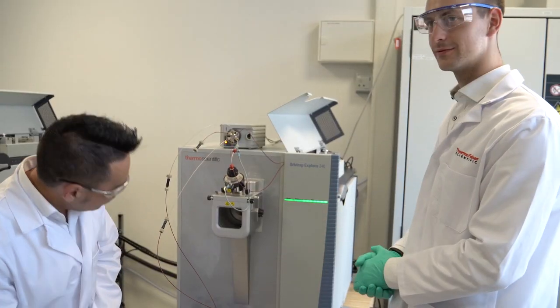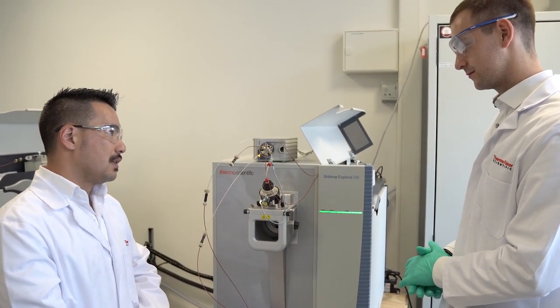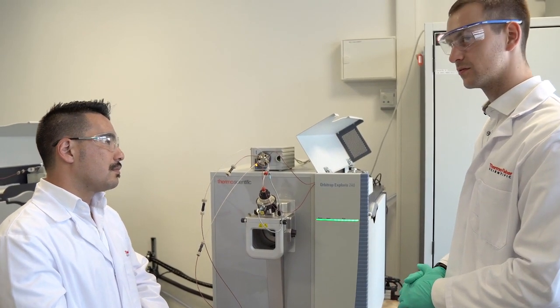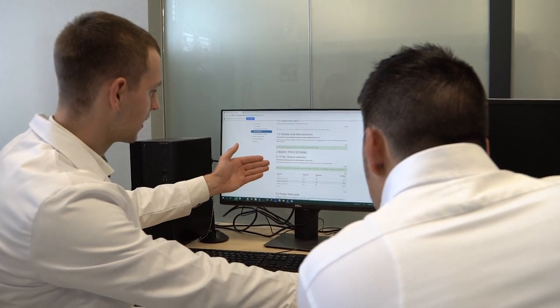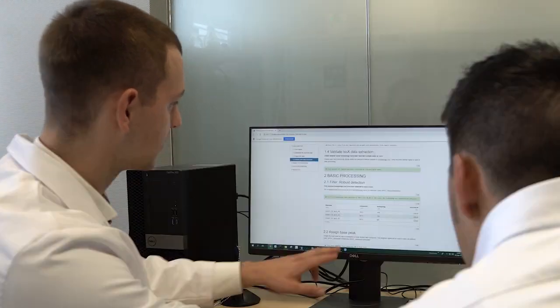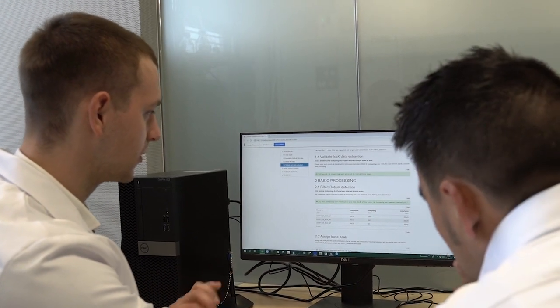Once the ions enter the Orbitrap, they will be analyzed and give us a high resolution accurate mass spectrum of nitrate and all its isotopologs within one spectrum. To calculate the isotope ratios out of the Orbitrap Exploris raw files, we use Thermo Scientific ISO-X application to extract all the parameters needed for isotope ratio calculation from the raw files. The dedicated workflow based in Orbitrap technology opens new dimensions in isotope ratio analysis.